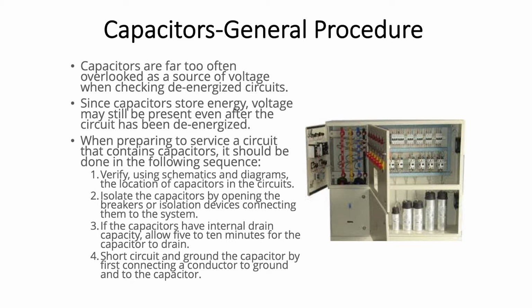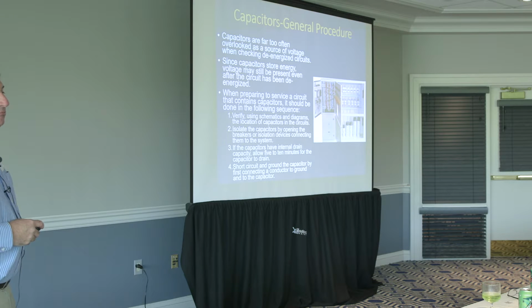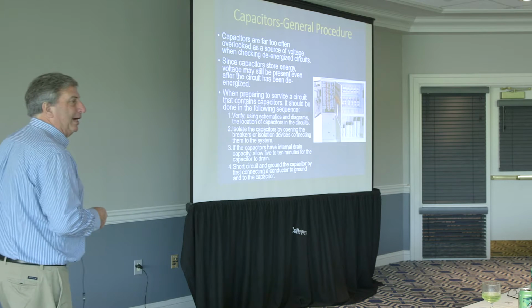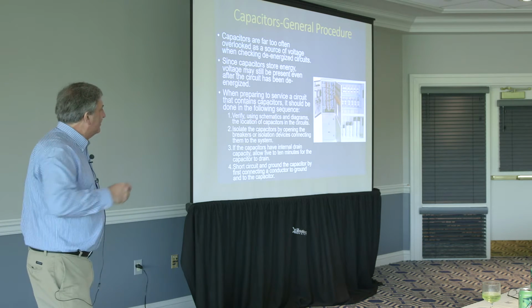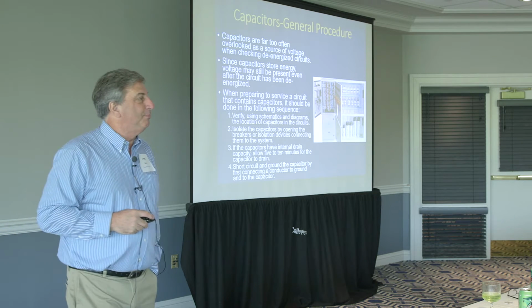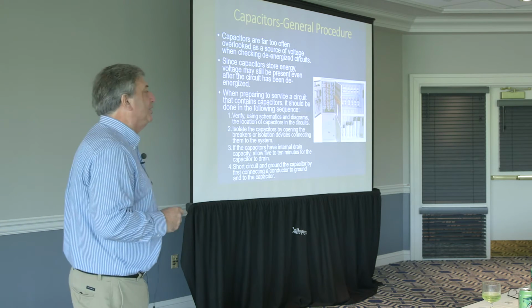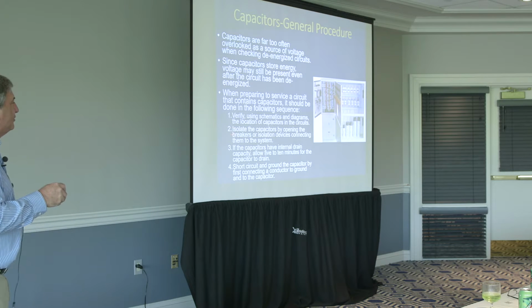So general procedure, often overlooked as a source of voltage when checking de-energized circuits. Okay? Most of you have probably had it drilled in your head. Not only do you essentially disconnect the circuit, but then you have to release stored energy in that equipment, wherever it is. Capacitors, no different. So, how do I know where all the capacitors are? You have to take me around to show me, or give me your schematics and diagrams. What if those aren't up to date? Okay. Potential issue.